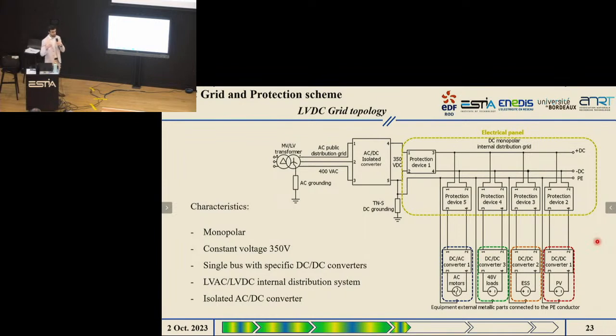In China, they are using this type of isolated converter. In Europe, they also separate the AC grounding from the DC grounding, sometimes using an LV transformer as well, using a two-level voltage source converter at the input instead of an isolated one. But everyone is making the same choices, because the little experimental tests we have nowadays show all the communities observing the same type of phenomena that disturb the operation of the AC-DC converter if we do not have galvanic isolation.